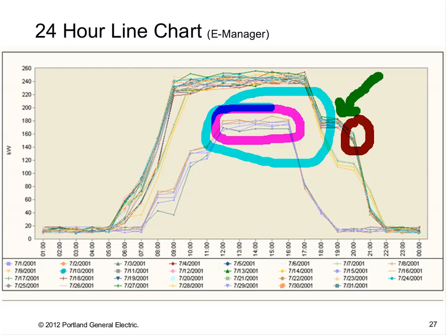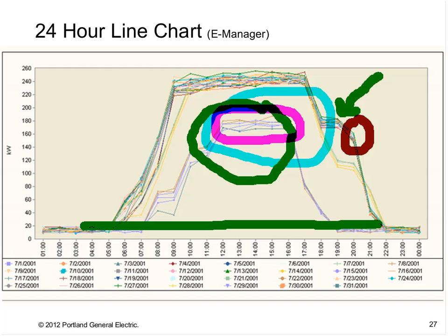This other good one in the middle here, you'll see a smaller load shape inside the bigger one. That is the weekend load. To me, this is very strange, because it looks like stuff is coming on. Maybe the HVAC is on, but no lighting. Looks like there's something going on, so I would ask if there was an event scheduled. Not really sure what's going on here, but this is a red flag, because the usage should be at base load on the weekends, and it should be off. So anyway, good finds, people. Very good.